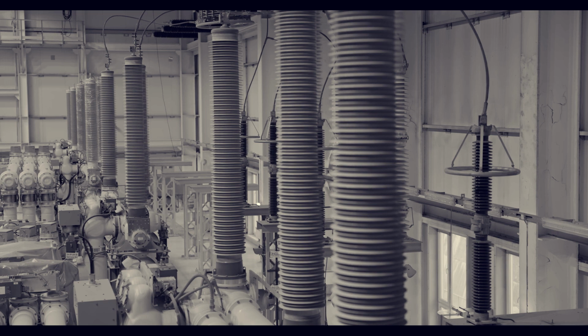When something goes wrong on the grid, a generator trips, a large load suddenly disconnects. The grid frequency starts to change. Instantly, there's now either too much or too little generation for the load. In a grid full of spinning machines, all that kinetic energy in all those rotors buffers the frequency. It changes, but slowly. The inertia buys time.